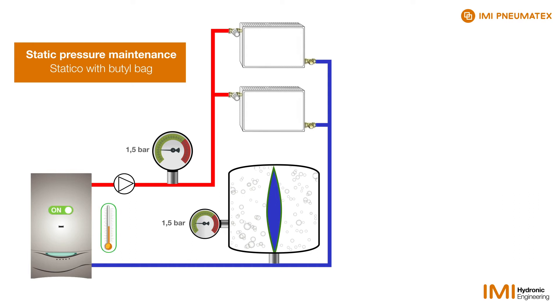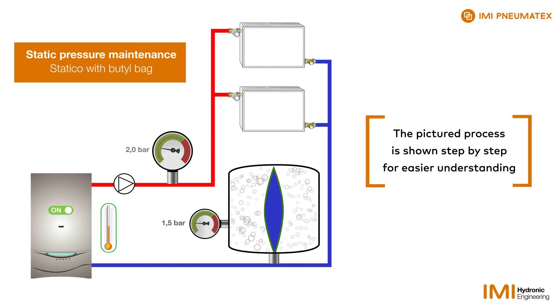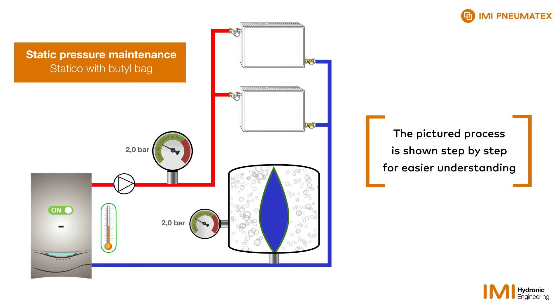Again, when the boiler is switched on, the water heats up and expands, resulting in a pressure increase to 2 bar, for example. Water is forced into the vessel and compresses the gas inside to 2 bar. The butyl bag expands evenly to give space to the incoming water.